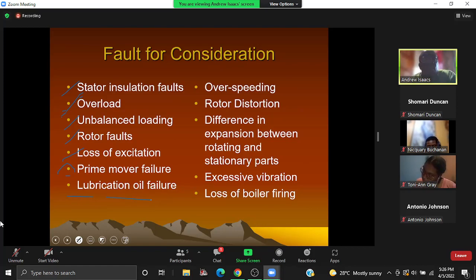Overspeeding, which now speaks to quality of supply. Yeah. Vibration. Well, I said rotor faults. This is more electrical faults on a rotor. The excessive vibration would come from physical damage to the rotor. Some mechanical faults on your rotor will cause that vibration.